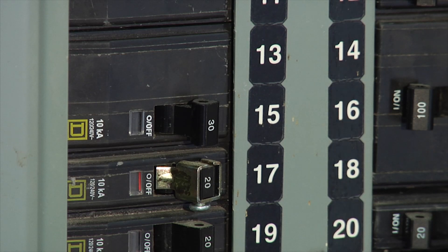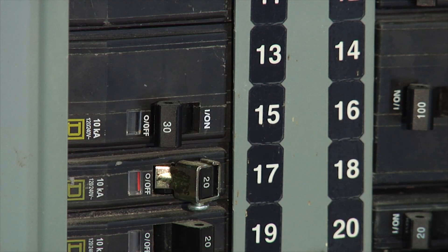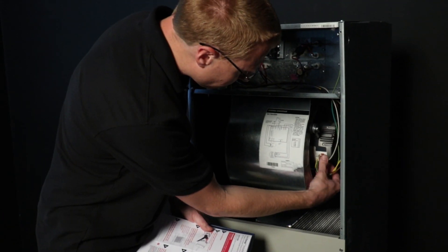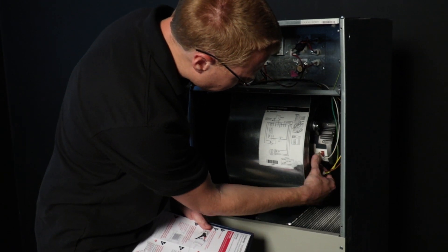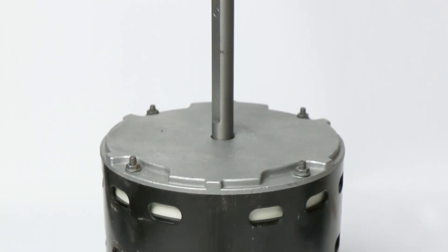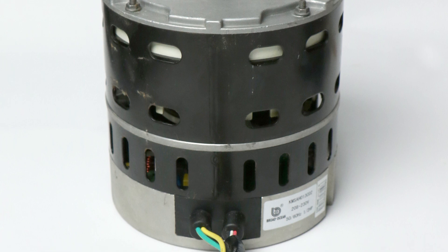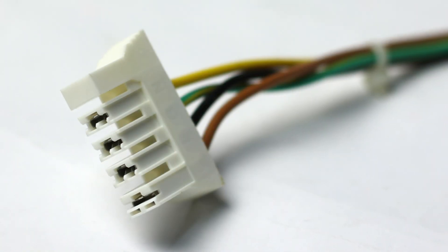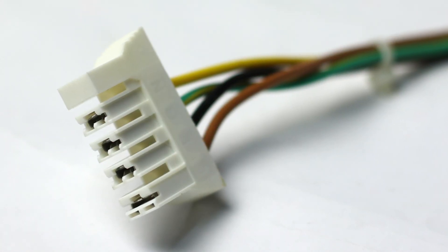The first thing you need to do is turn off power to the air handler. Verify that you have a constant torque blower motor such as an X13 or SelecTech constant torque ECM motor. These types of motors typically have a plug that looks like this and one or multiple thermostat wires attached to them.